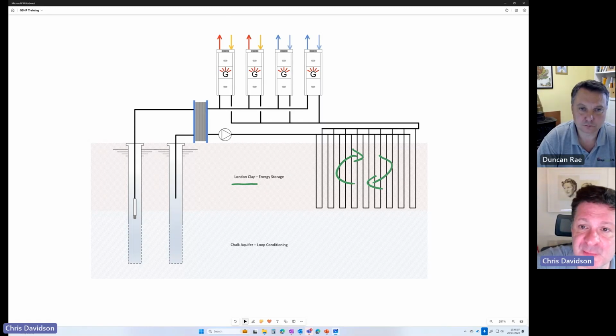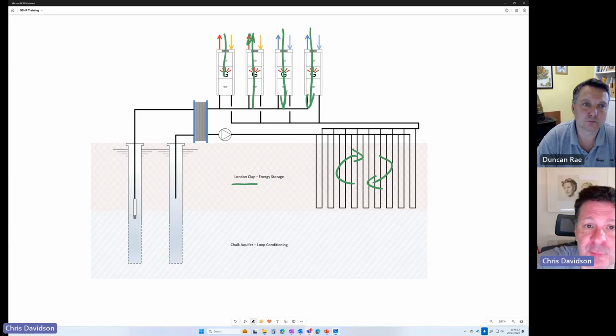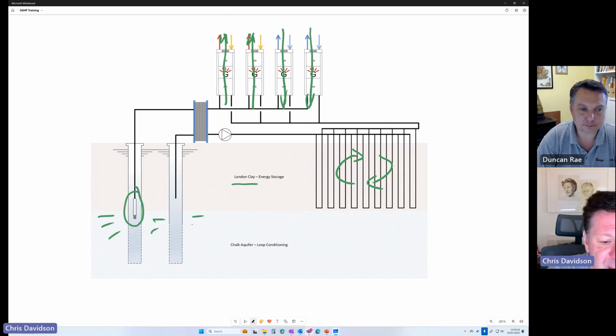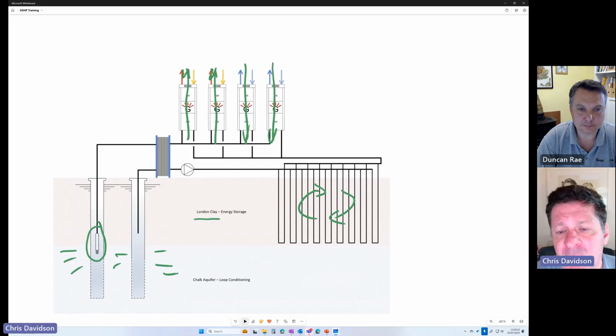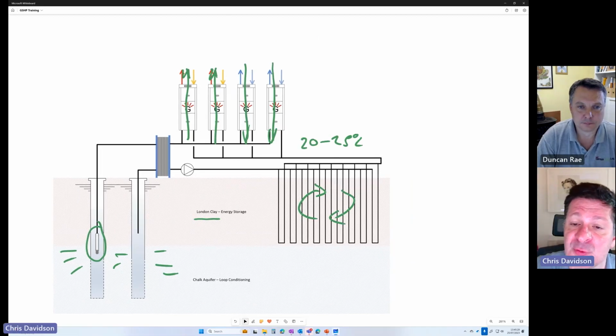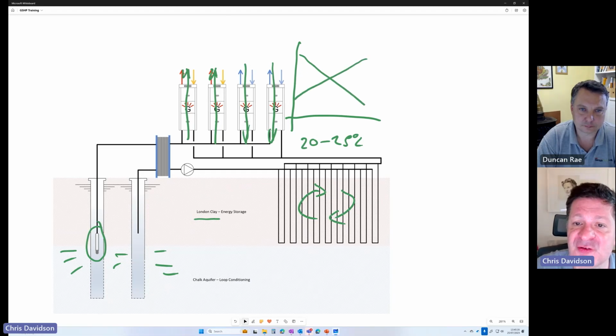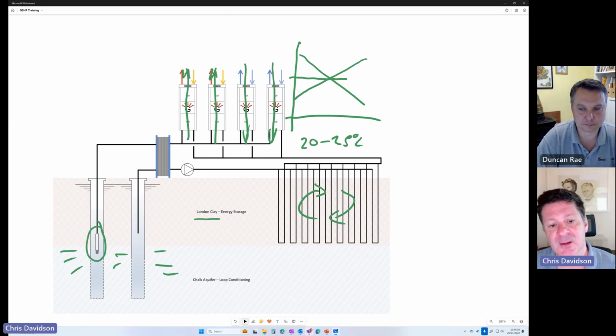It's a bivalent system, so we can schedule cooling and heating loads on and off of the system to take heat out or put heat back into that ground loop. We can also use our water wells here, which utilise the water that's in the cracks and the fissures in the top of the chalk, to temper that ground loop. What we're doing is managing that ground loop between 20 to 25 degrees C most of the year. The reason we've picked that point is that if you draw a graph of these particular heat pumps in heating and cooling mode, the efficiency crossover is at that 20 to 25 degrees point.